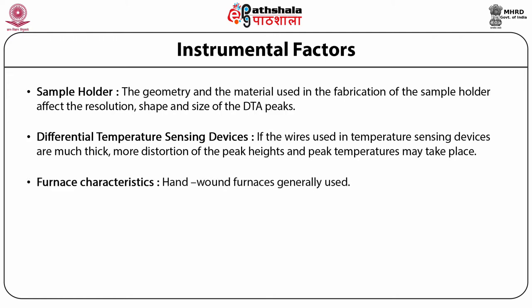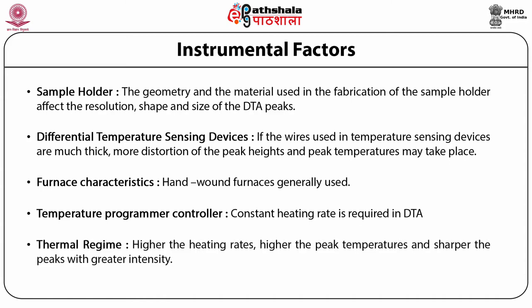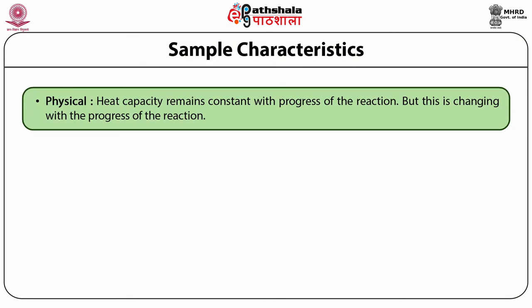Furnace characteristics: the type of winding shows a direct effect on the DTA curve. If the winding in the furnace is not uniform, the baseline is changed — this is generally seen in hand-wound furnaces. Selecting the temperature programmer/controller is very important because a constant heating rate is required in DTA. Thermal regime: the heating rate has a great influence on the DTA curve — higher the heating rate, higher the peak temperature and sharper the peaks with greater intensity. Generally, heating rates of 10 to 20 degrees per minute are employed. The effect of particle size is related to packing density and overall thermal conductivity; particle size changes peak area, peak temperature, and completion temperature.